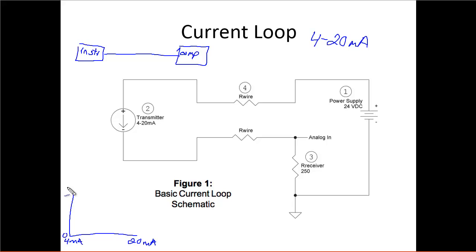And then that's going from zero to however many values, like in my 20-bit example, 1,048,576. So why do they do this? Why not just do a voltage or something like that? Well, it turns out that if you do a voltage, you're going to get more noise if this wire is going through a particularly noisy environment, you're going to pick up noise, you're also going to have a small voltage drop across the wire, so your signal coming into the computer would vary based on how long this wire is, and of course you don't want it to be dependent on the length of the wire, you don't want to have to calibrate it to the length of the wire.